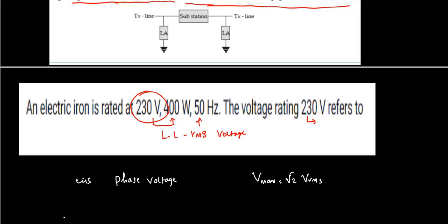Based on the phase voltage. Okay. So what is the reference for designing insulation? Means switched voltages. Okay. Switched voltage means there is surge voltages. You have two types of surge voltages: external over voltages and internal surge voltages. So we design insulation based on the internal surge voltages, switched voltages.